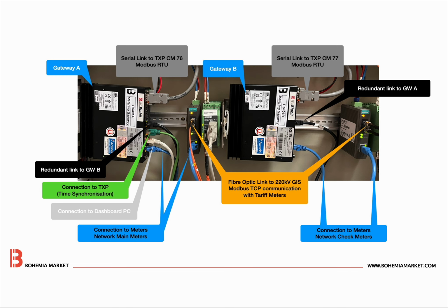To bridge this gap, a gateway is introduced between the new meters and the existing control system. On one side, it communicates with the meters using their native protocols. On the other side, it presents the data in exactly the same way as accepted by the existing DCS or SCADA systems. From the control system point of view, nothing changes. No logic is modified and no engineering intervention is required.